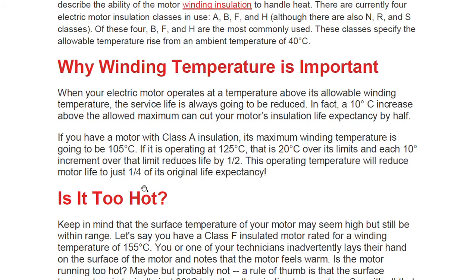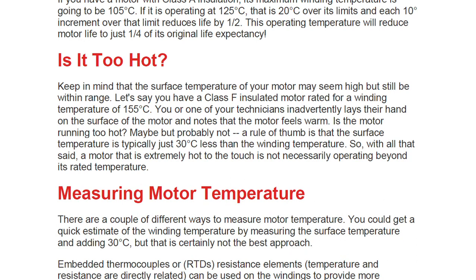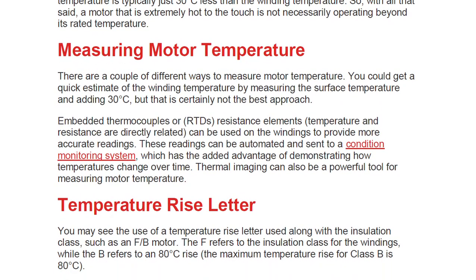Keep in mind that the surface temperature of your motor may seem high but still be within range. When you touch a motor it may feel very hot, but it can still be within the allowable temperature range. For Class F, that range is around 155°C, so a technician laying hands on the surface and finding it hot does not necessarily mean it is out of range.